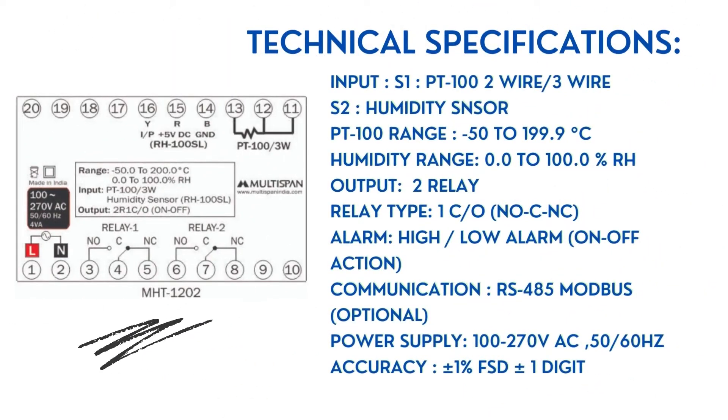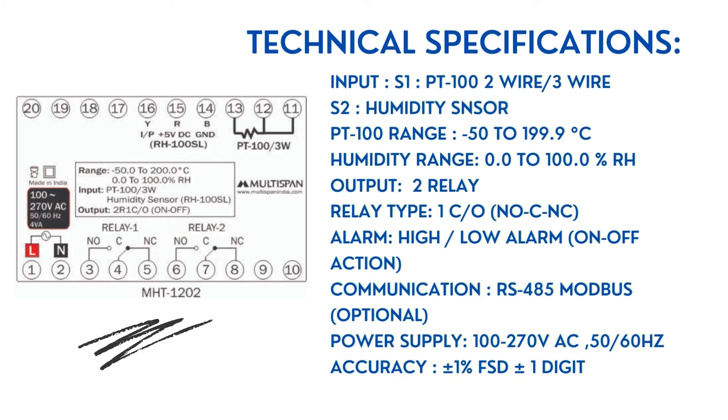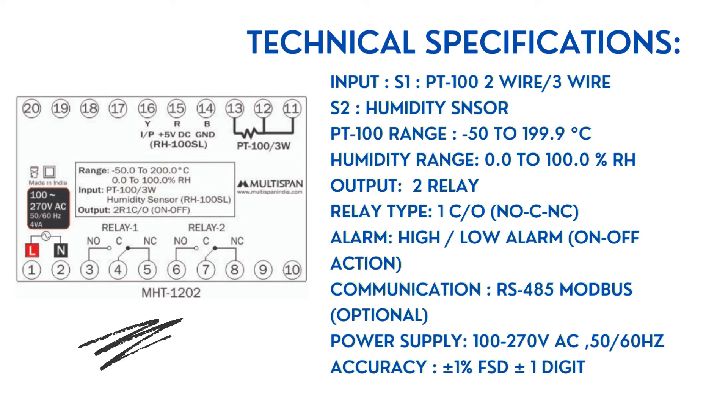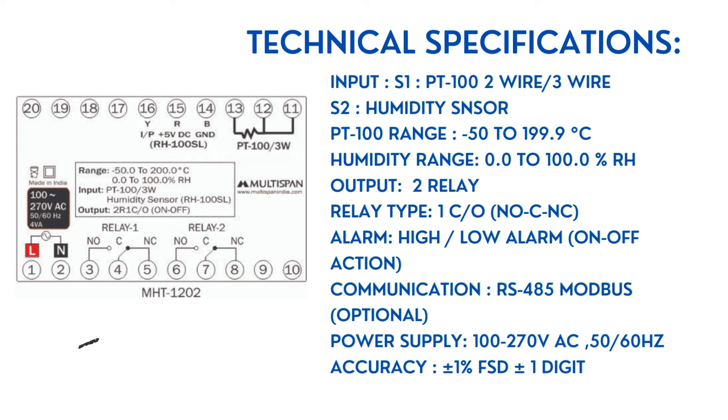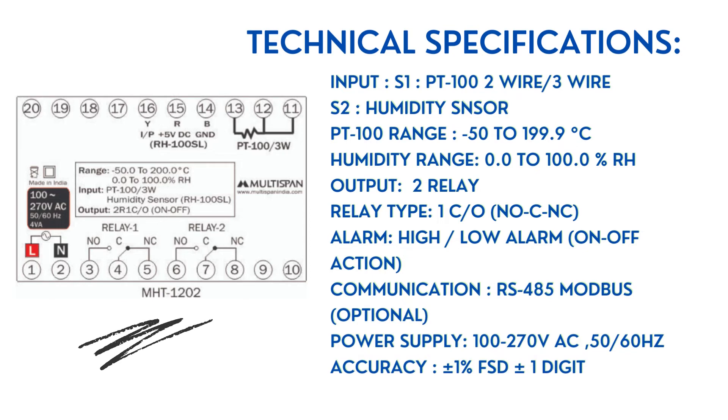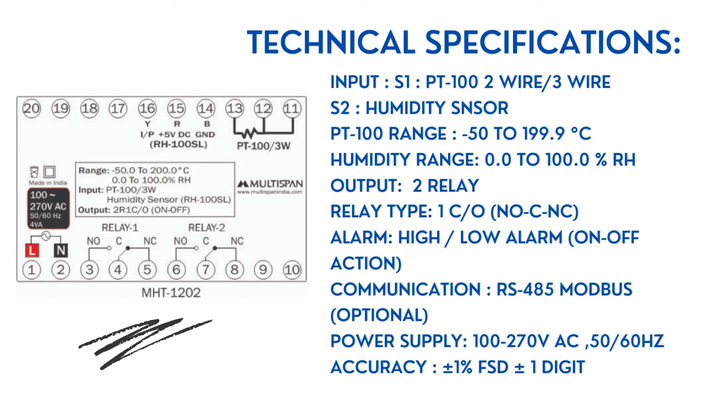Technical specifications: Input S1 is PT-100 two-wire or three-wire. S2 is humidity sensor. PT-100 range is -50 to 199.9°C. Humidity range is 0.0 to 100.0% RH. Output is 2 relay. Relay type is 1 C/O (NO-C-NC).